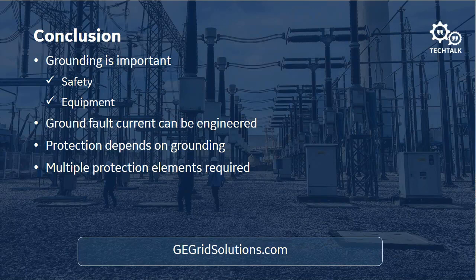For example, in a CT circuit, you usually have one safety ground, which is usually in the residual connection of the CT. If you mistakenly apply two grounds, or an insulator breaks down and gets shorted to ground, you have two grounds in your CT. When you have a ground fault, there's a ground potential rise, a potential difference between those two ground points, and they can cause currents to flow in that CT which would not otherwise flow. And it can cause issues for the protection elements in that CT circuit. So grounding is important not just on the primary process equipment, but on our secondary equipment.